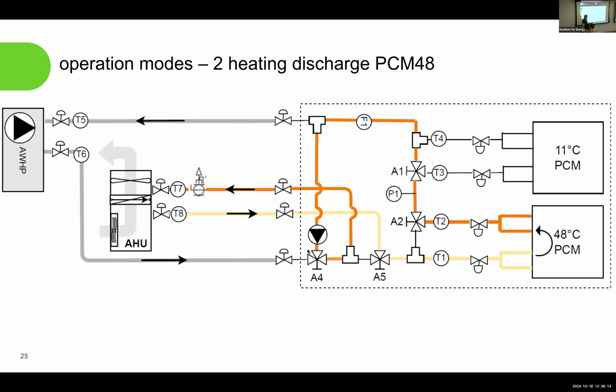We'd use a different pump here. There's a pump in the air-to-water heat pump, and then a separate circulator pump that moves fluid round in a circle through the air handler, back round through the battery, heats up, comes back round, goes through here, around here, through the air handling unit, and then gets cooled down again. I tried to keep this consistent with how it's structured in the box, so this represents the valve on the left and this represents the valve on the right. It could have been greatly simplified, but it makes sense if you're actually looking at the physical system.